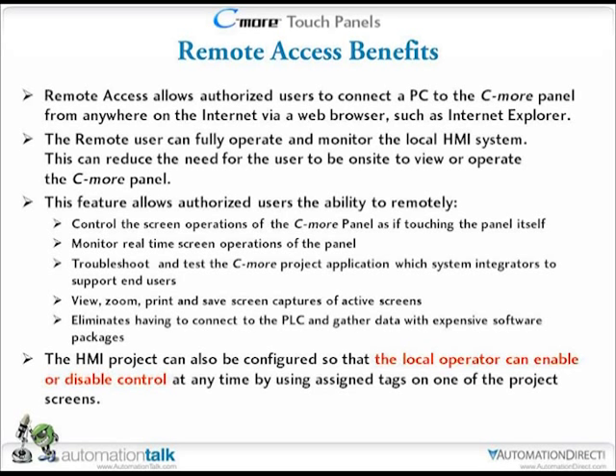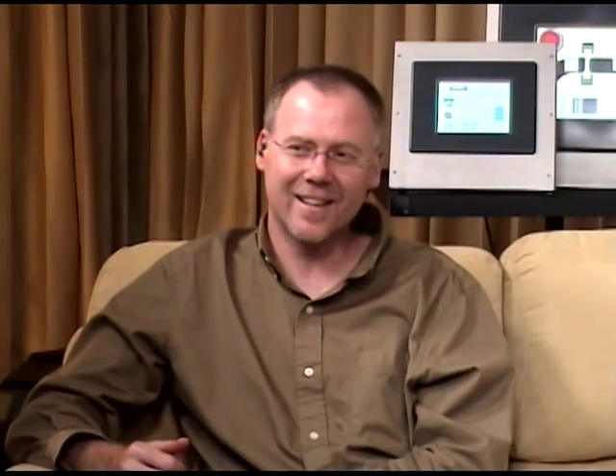The HMI project can also be configured so that the local operator can enable and disable control. This is very important — feedback from OEMs during beta testing was that they wanted to be able to disable remote access. Say somebody's taking over control of the touch panel remotely, but the operator standing there needs to do something with that machine. It could be configured so that person can take back control. We want to make it as safe and secure as possible for the end user.